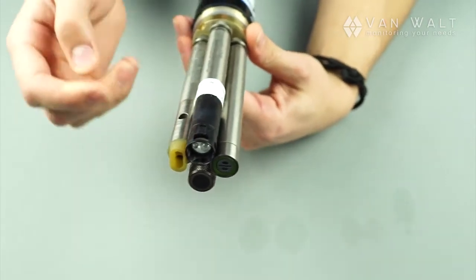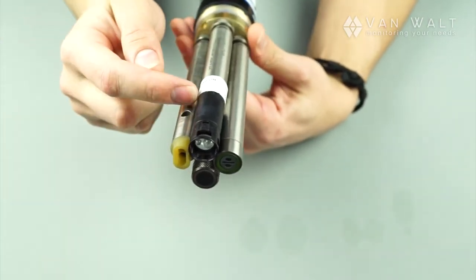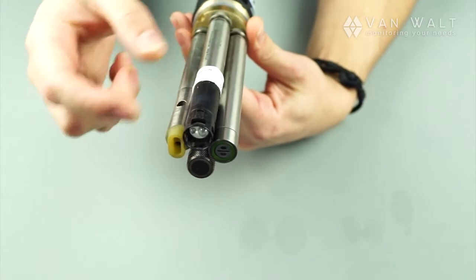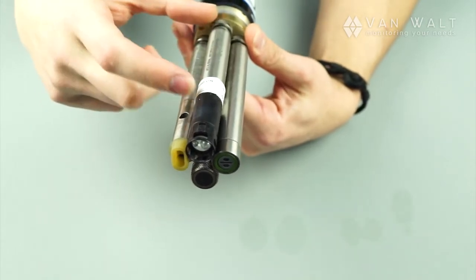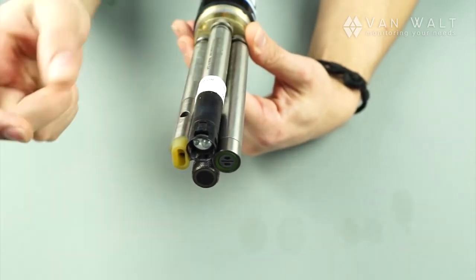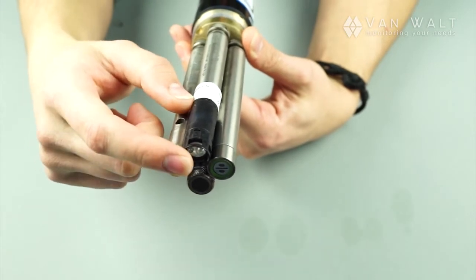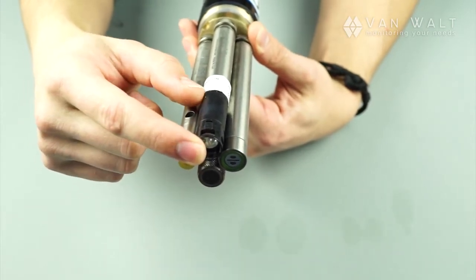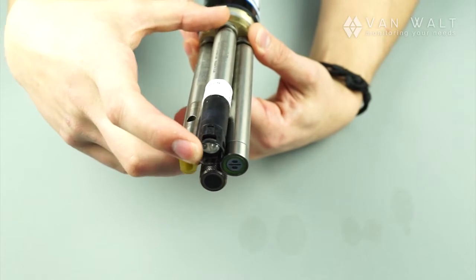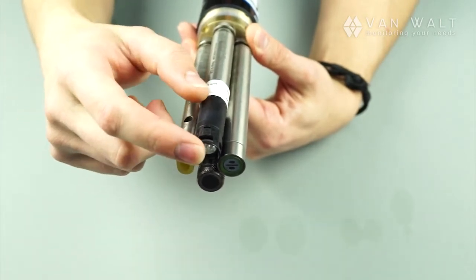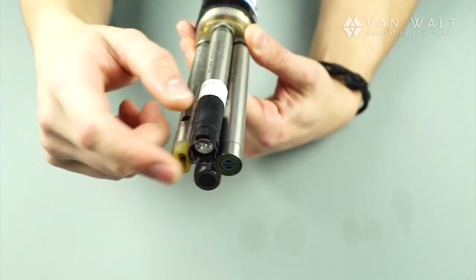When it comes to pH, just this tip is replaceable. So the computing functions are done in this part of the probe, but the electrode itself is just this black tip. If you have any problems in the field, there's no need to replace the whole probe, just the tip here, and that actually makes it even more economical to change than the conventional YSI.